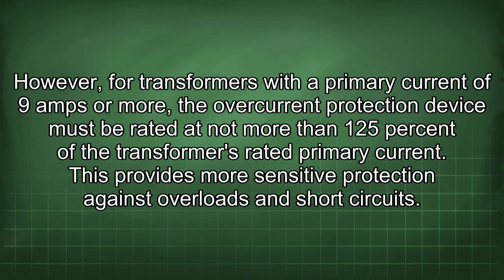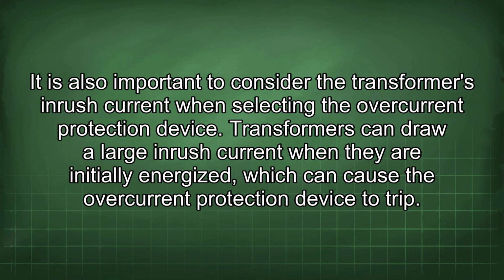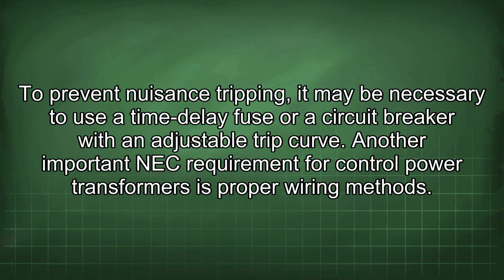This provides more sensitive protection against overloads and short circuits. It is also important to consider the transformer's inrush current when selecting the overcurrent protection device. Transformers can draw a large inrush current when they are initially energized, which can cause the overcurrent protection device to trip. To prevent nuisance tripping, it may be necessary to use a time delay fuse or a circuit breaker with an adjustable trip curve. Another important NEC requirement for control power transformers is proper wiring methods.